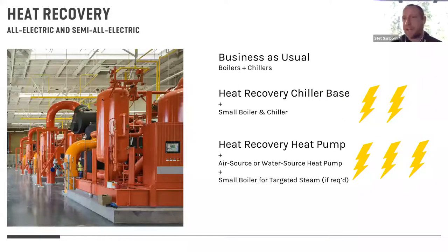And then we are still augmenting those projects with really small, targeted, gas-fired boilers. And that typically is around the sterilization component. So depending on what the throughput is and the steam demand for sterilization, that right now, in both labs and in our healthcare work, is still an area that we haven't done a great job of cost-effectively electrifying. Electric boilers, at least for us and our utility rate structure, can't compete with gas because it's essentially electric resistance. So it's one for one.